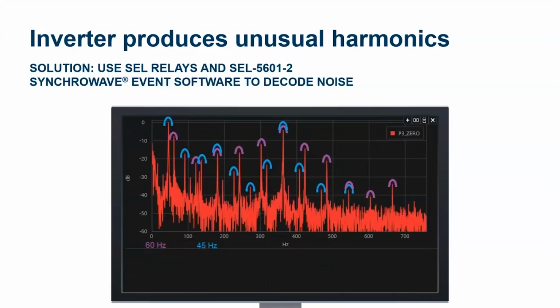Now, inverters, generators, and engines, especially reciprocating engines, and especially inverters, can create harmonics on our AC power systems. For me, I had never decoded the harmonics that I've seen on power systems for decades until recently. And here's a plot that again we produced using our SynchroWave Event software, again capturing events from a 700 series relay.